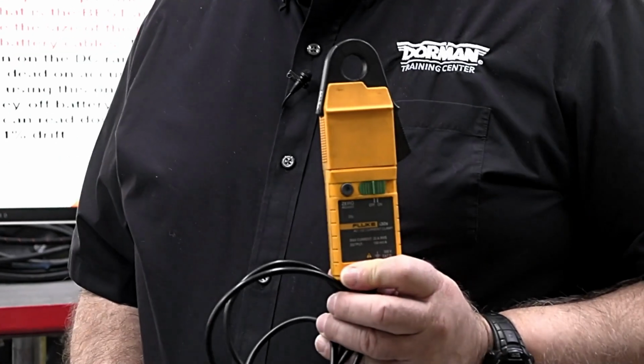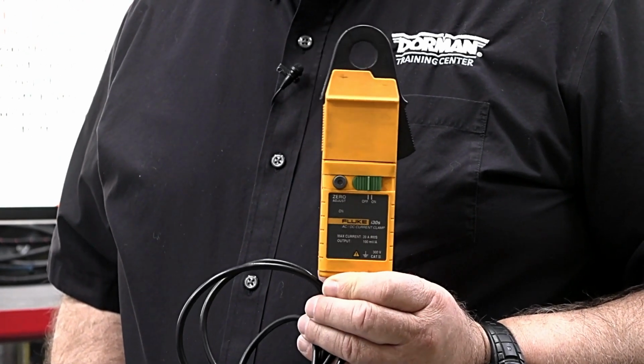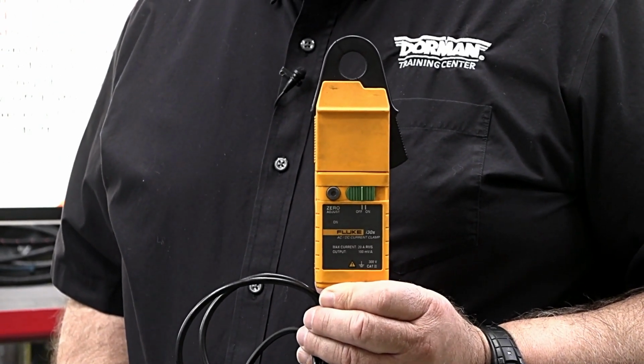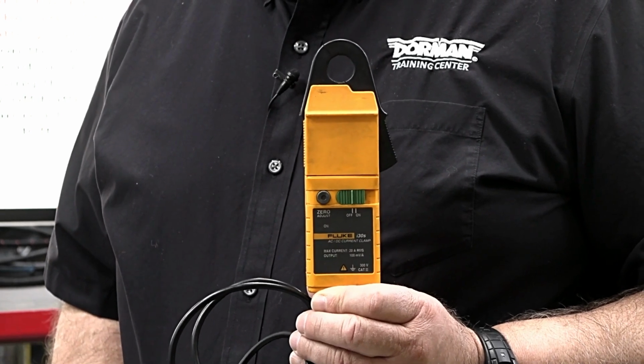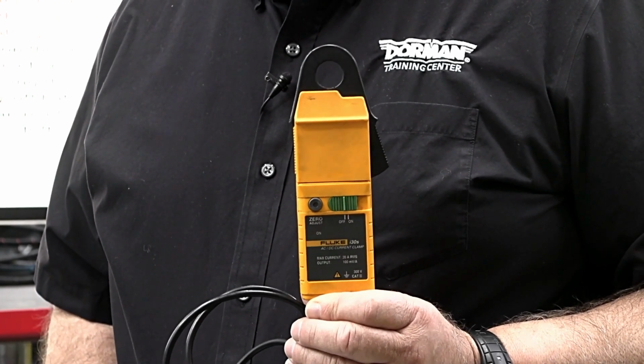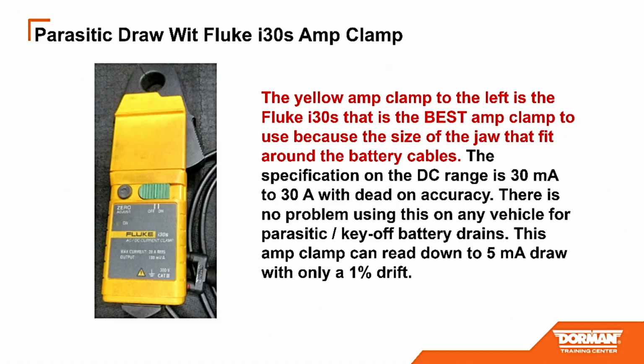It is an I-30S. Be careful, they make another clamp that looks real similar, but this is the I-30S - you can see up here on the screen, this yellow amp clamp to the left is the Fluke I-30S. That is the best amp clamp to use because of the size of the jaw that fits around the battery cables. Specifications: DC range is 30 milliamp to 30 amps.